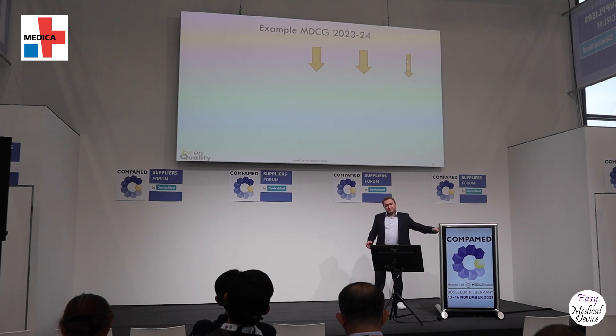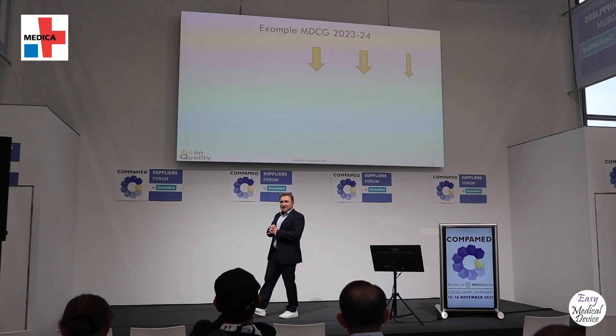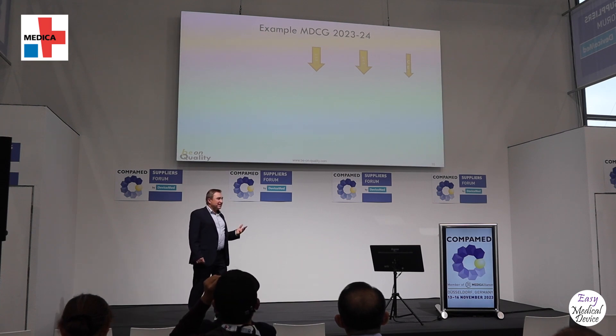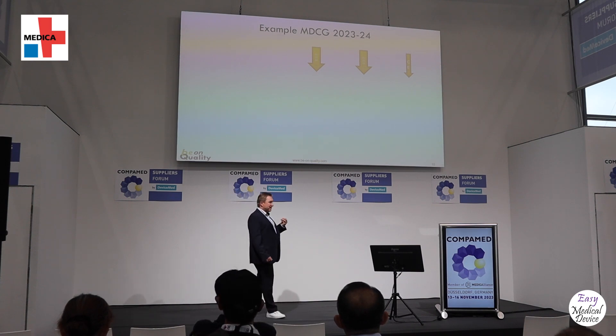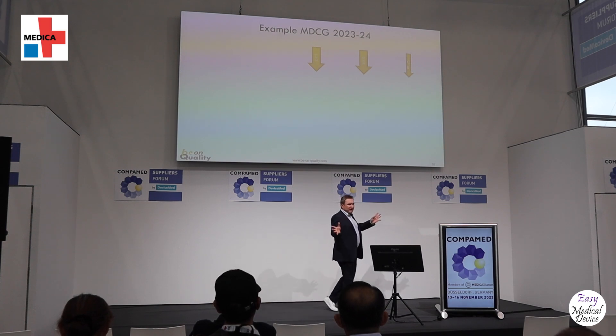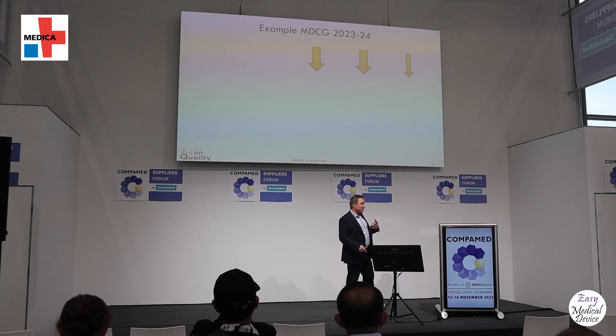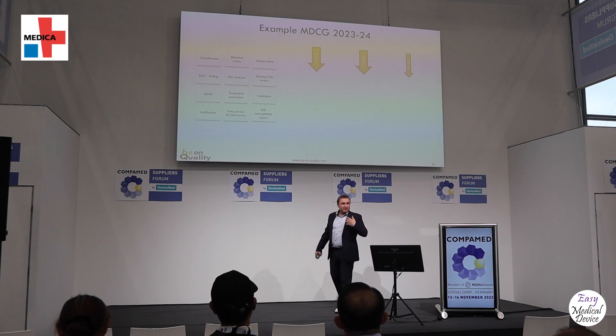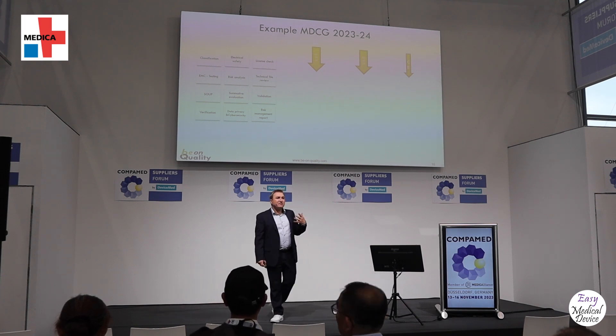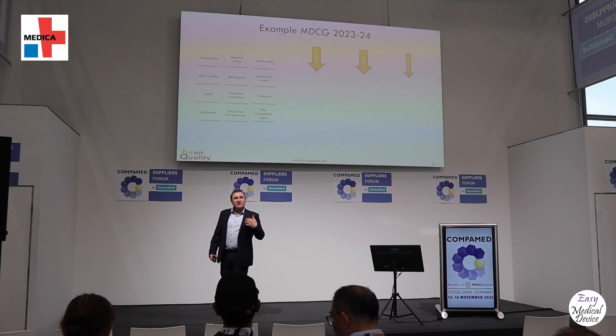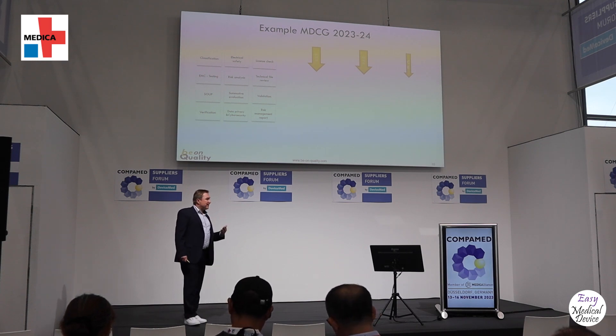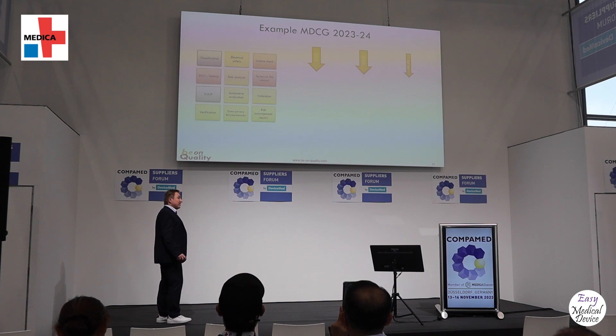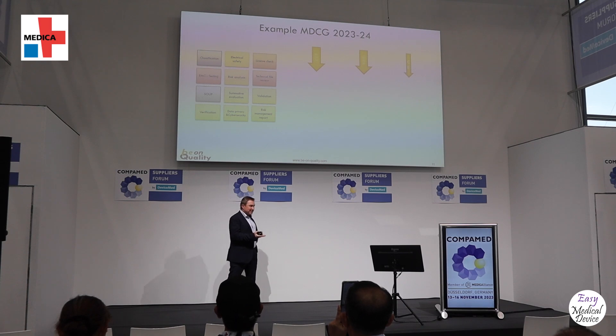As one example, I want to share the current MDCG guidance document about medical electrical products that are not medical devices but can be used together with medical device software — which is great. It's a non-binding recommendation, however it gives us a lot of information about what needs to be covered. As a regulatory affairs manager, you go through the guidance and say: where does it have my impact? What do I need to handle at a certain point in time? I went through it and found that some topics in my overall procedure can be impacted, and others not.